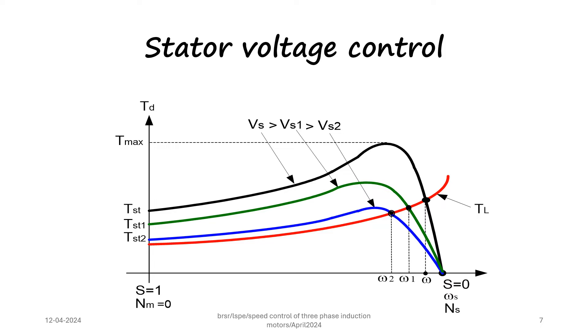The torque-speed characteristics for stator voltage control are shown here. As the voltage increases, the torque developed by the motor increases. For the supply voltage VS, the torque-speed characteristic is shown by the black line. When the voltage is decreased, the characteristic shifts to the green line, and when decreased further, to the blue line. The speed at which maximum torque occurs remains more or less the same — the change in supply voltage does not affect the point at which maximum torque occurs.